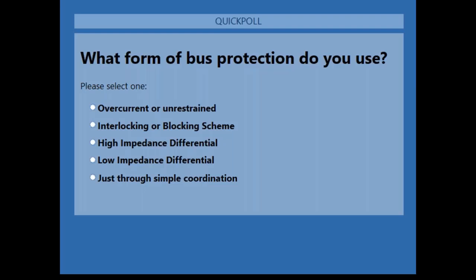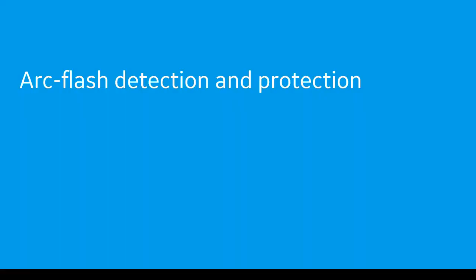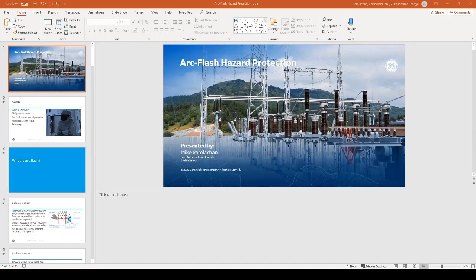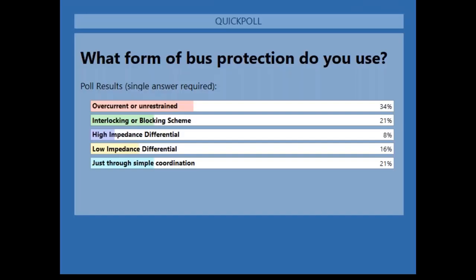Before we talk about zone interlocking, one of the techniques that I'm not going to talk about, which is on the poll, is the overcurrent or unrestrained differential. Basically, it's just a bunch of CTs paralleled together, like in this case, all the CTs from the main and all the CTs from the breaker, paralleled together and going into an overcurrent relay.